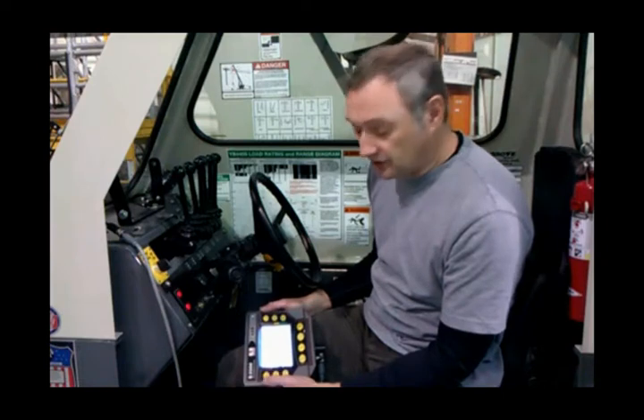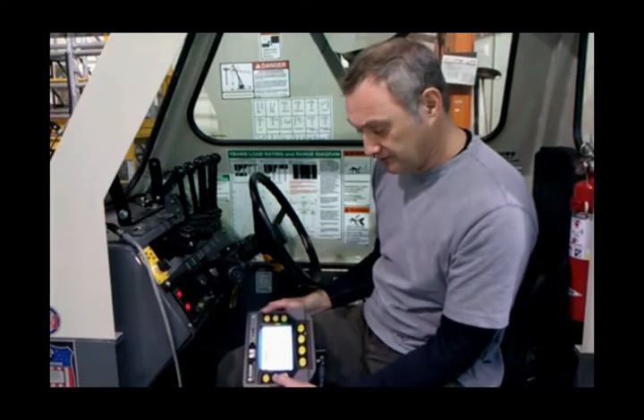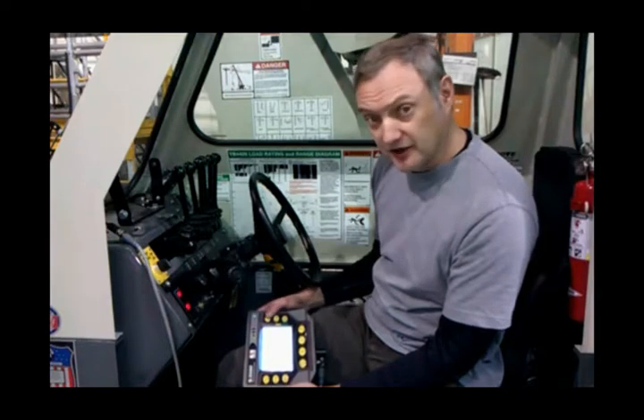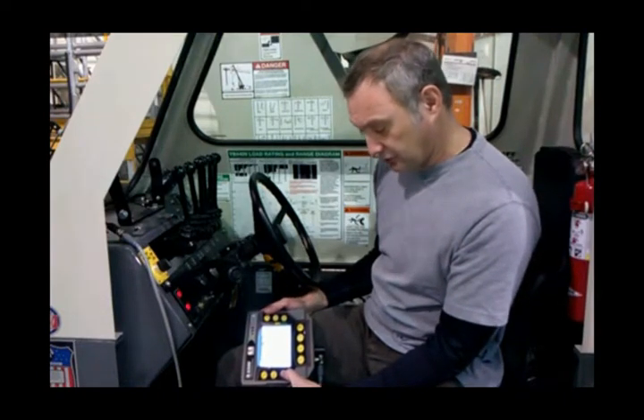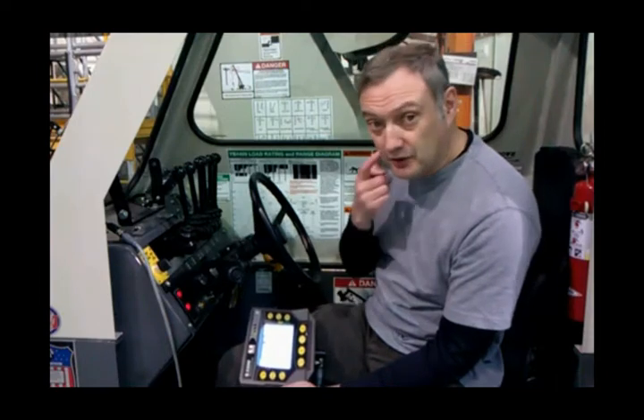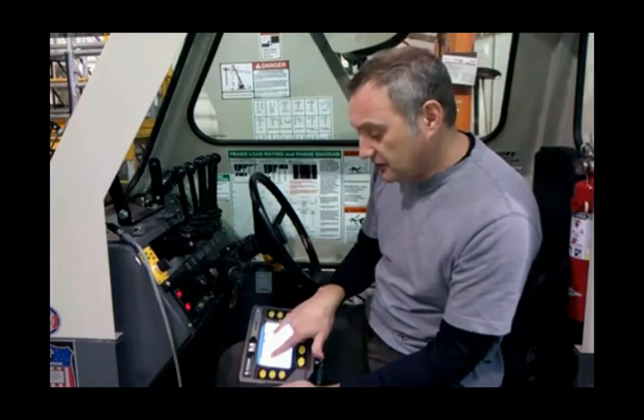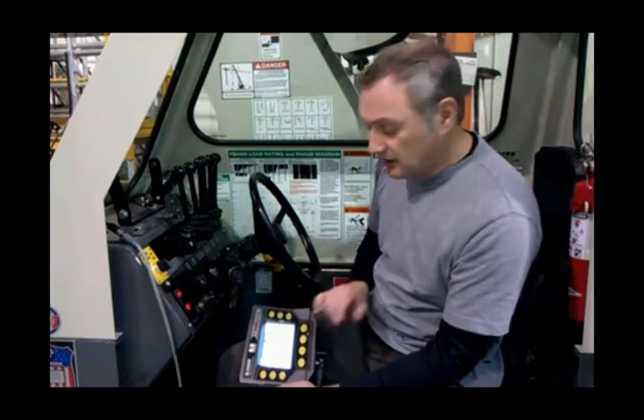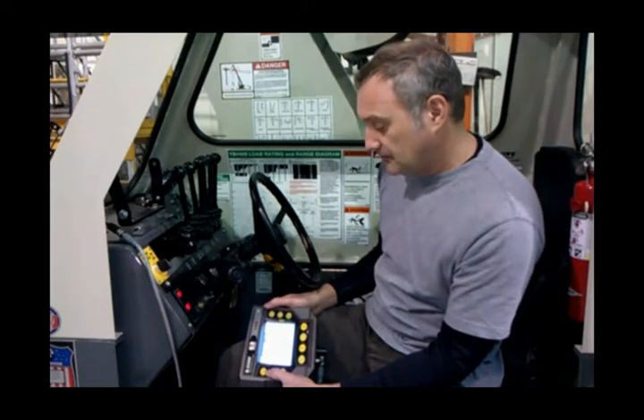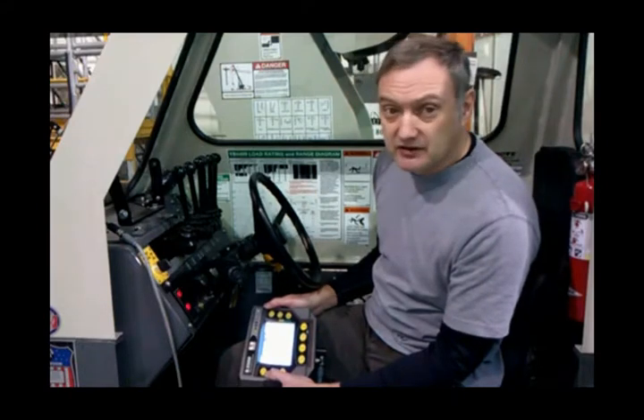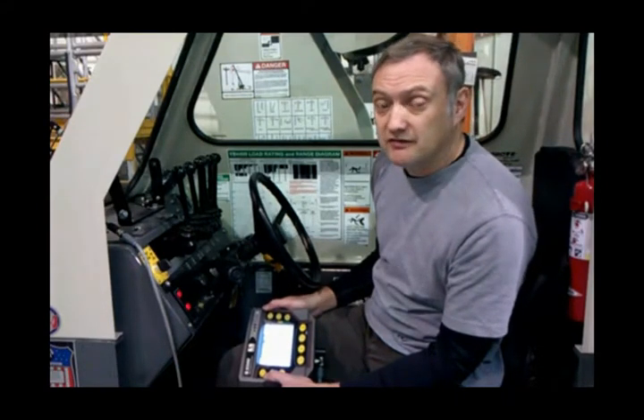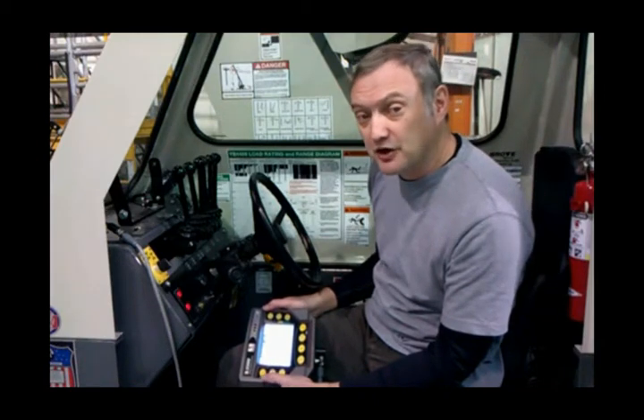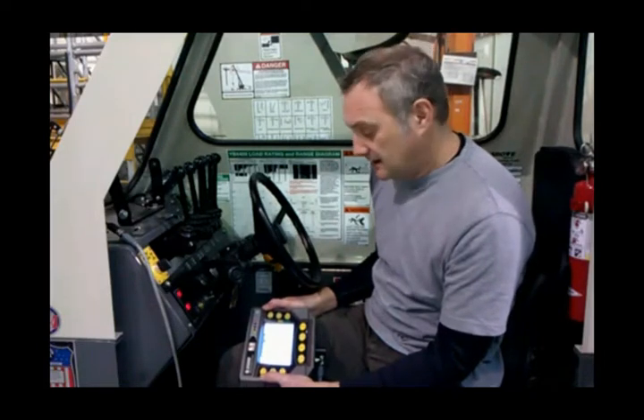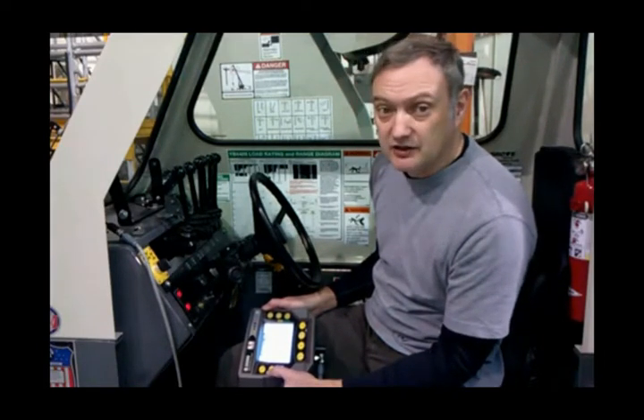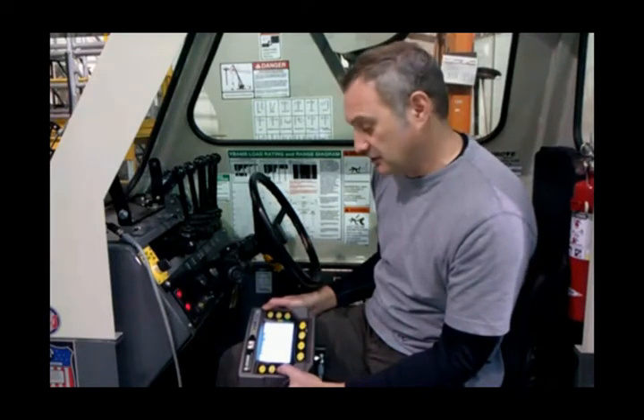Let's go back to diagnostics and take a look at what we have. So we're going to hit button 1, going to use button 2 to get us to highlight diagnostics, and then hit the check mark. Then we're going to scroll down using button 3 to TX0 and TX1. What we have here is both are indicating -2. So we're going to actually calibrate both of these. Section 7 of the troubleshooting guide will tell you that the value when the boom is all the way down and there's no pressure in the cylinder should be between 0.0 and 3.0. If you're above or below that value, then the system is not going to give you an accurate weight measurement.